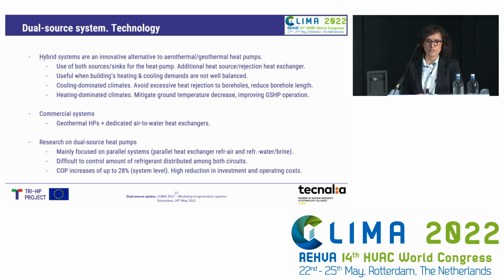Normally, the commercial systems use, as I said, geothermal heat pumps plus a dedicated air-to-water external heat exchanger. Some research has been done on dual-source heat pumps, and this research is mainly focused on parallel systems, in which a parallel heat exchanger between the refrigerant and air and the refrigerant and water or brine is included. What is claimed in the literature is that it's difficult to control the amount of refrigerant distributed among both circuits, so these systems are difficult to optimize and to operate.